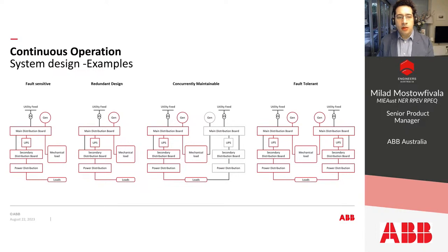What I have prepared here is a few system design examples for your reference in terms of continuous operation, which I believe you can benefit from as a key takeaway from today's session. The first type of system design example is a fault sensitive type of design, as you can see on the left hand side of your screen. The second type is a redundant design, where you are able to provide a redundancy factor within your system. And third is the concurrently maintainable type of design.